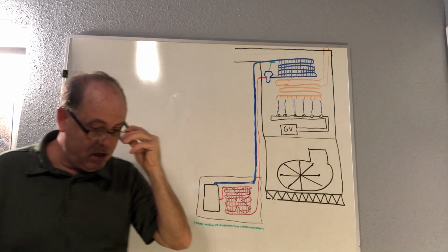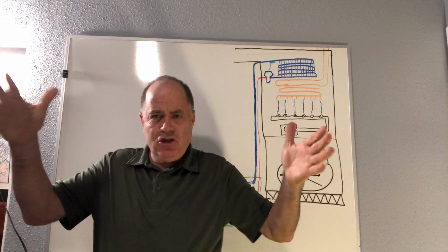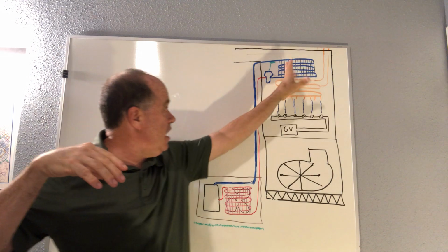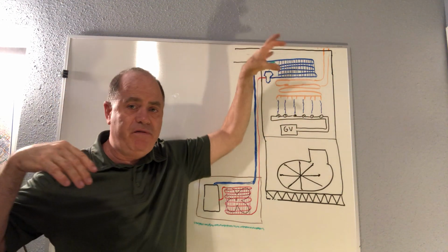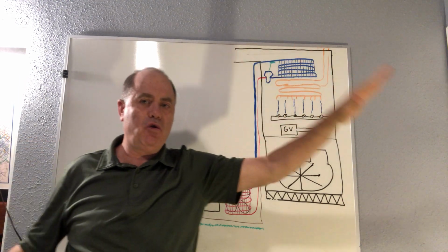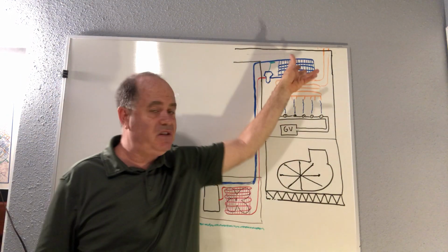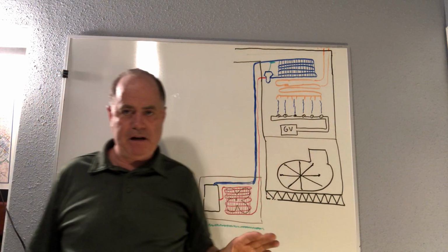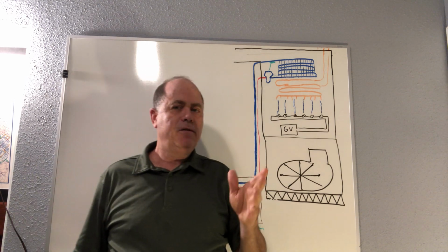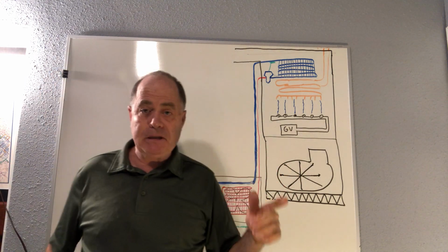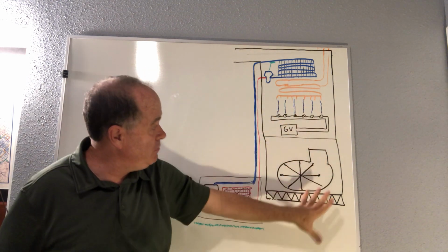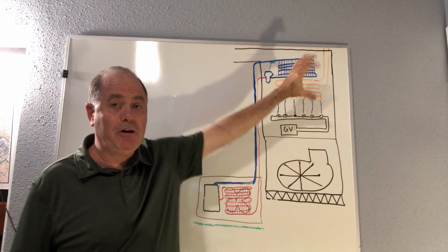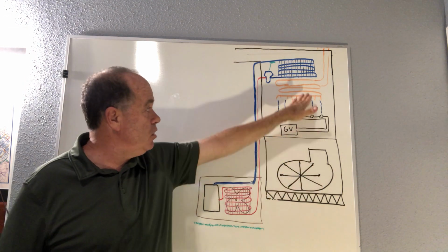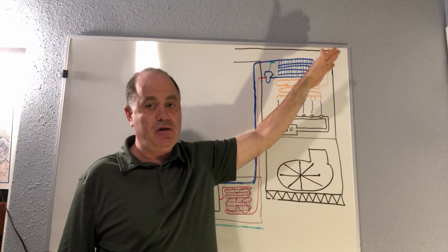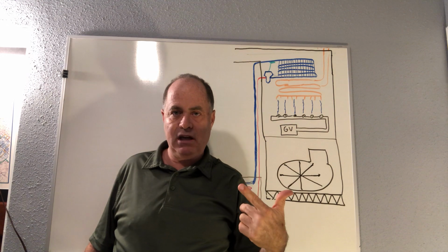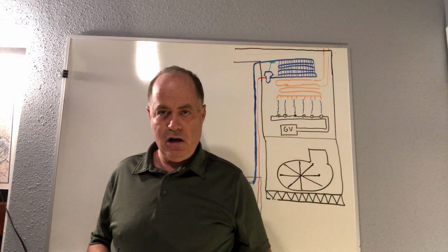Now, the other point I wanted to make was, on a package unit, where everything's in a package on your roof, you generally have the opposite. You generally have the air going over the evaporator first and then across your heat exchanger, so that you don't have this scenario, because you don't have all this extra room to dissipate the pressure. So the design is usually a little different for a package unit than some split systems, where in a split system, quite often the heat exchanger is upstream where the air hits it, and then that hot air hits the evaporator coil. We flip the script a lot of times for a package unit where the air goes across the evaporator and then the heat exchanger, and then if it heats up, it's just going out the ductwork and you're not warming your evaporator. Hidden knowledge.